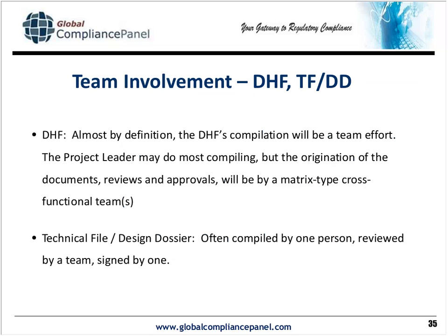Now, for design history file, generally the project team will supply the documentation and a lot of the information, but usually a project leader or individual designated by that project leader would do the compiling of it. It's generally more of a one-person job to compile, but the preparation of the documentation obviously is part of an entire team effort. A technical file design dossier, generally that's often compiled by one person. Generally it'd be reviewed by a team and signed by a high official in the company.